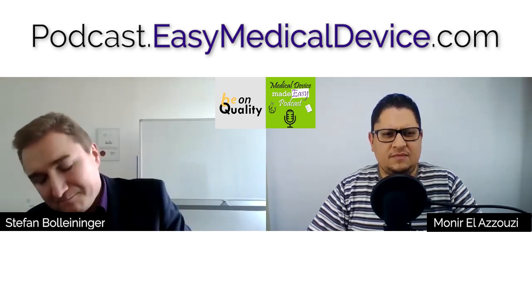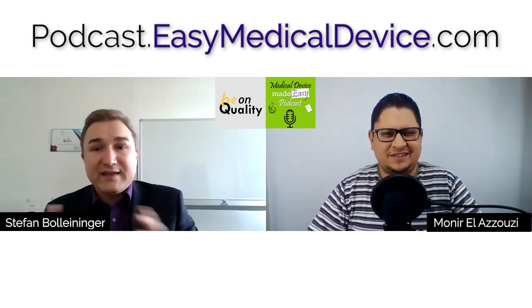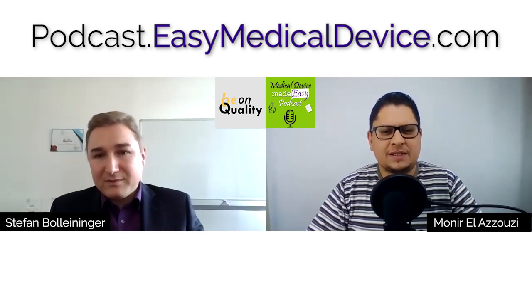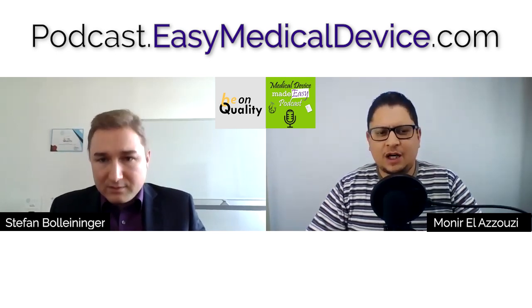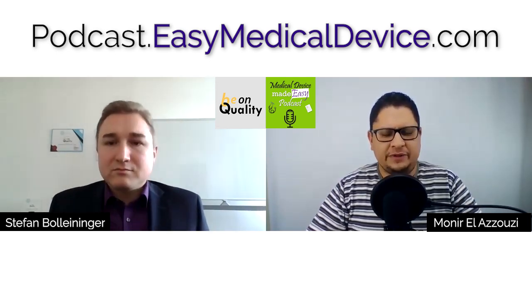So they need to have a surveillance audit and a shorter surveillance audit. So the first audit is a certification audit, then it's the first surveillance, the second, the third surveillance, and then it's a certification again, because the certificate is only valid for 5 years. Okay, 5 years. Yeah, the certificate is valid for 5 years. They are coming every year, and they are covering all the quality management topics within this period. That is correct.